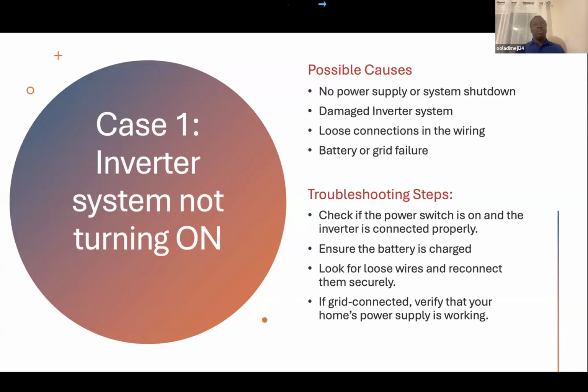Client calls and says, "Oh, the inverter is not coming on. What happened?" And you just realize that the inverter switch is off. Who turned it off? They don't know. But it happens. If you are not careful, you start uninstalling, checking cable trays, pulling out, measuring and all. And at the end of the day, you spend 3 hours looking for nothing, just to see that it's just the inverter switch that is not on. It happens. I've seen it happen. So then ensure the battery is charged.